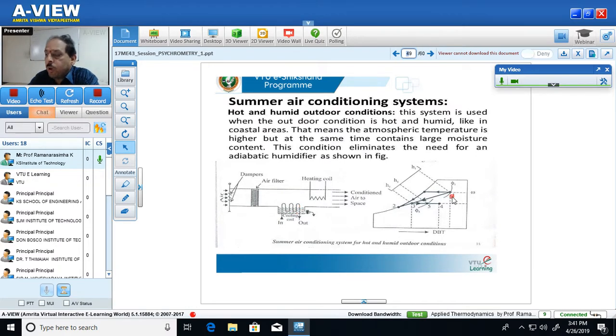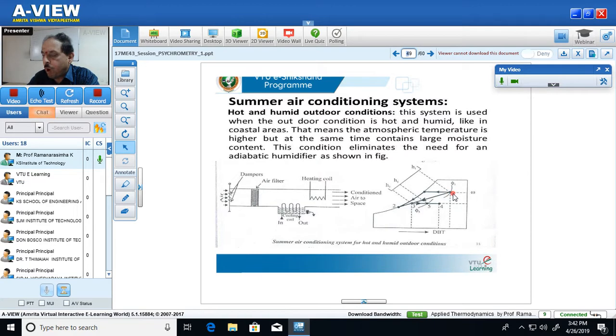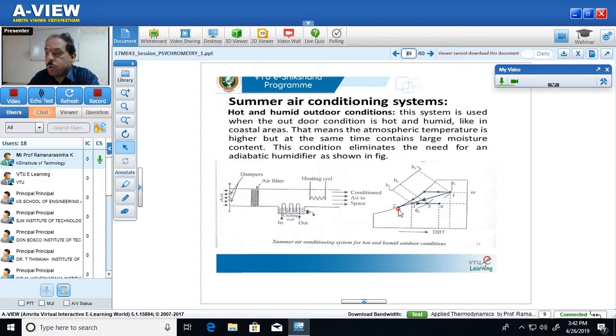This process can be represented in two ways on the psychrometric chart. One way: move from point 1 horizontally to the saturation curve — that is cooling — then from that point on the saturation curve down to point 2, which is dehumidification. During the horizontal movement, temperature decreases. Moving along the saturation curve downward, specific humidity also decreases. Alternatively, you can move directly from point 1 to point 2.